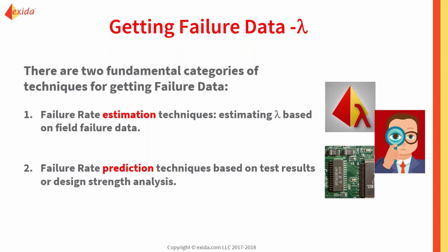Let me give you some examples of estimation techniques. This is going to be field failure reports or information from manufacturers' data. This could be field failure information from end users. This could be database studies, something like exida. The great thing about the estimation technique is it is based on real and historical data. However, if you're using a large database, you don't have specific information per device or per application. And if you are an end user or a manufacturer using field failure reports, you might not have enough of this information available to make statistical analysis sense.